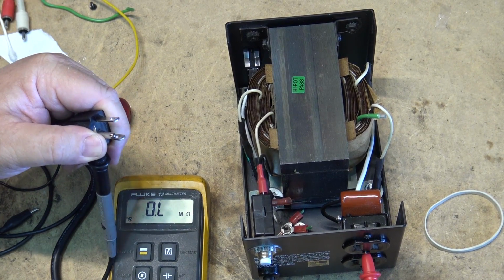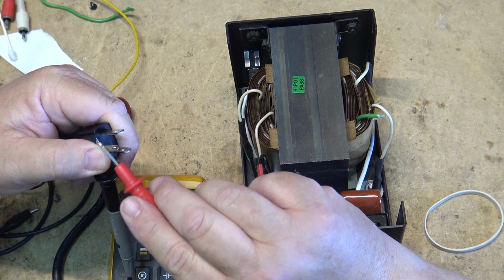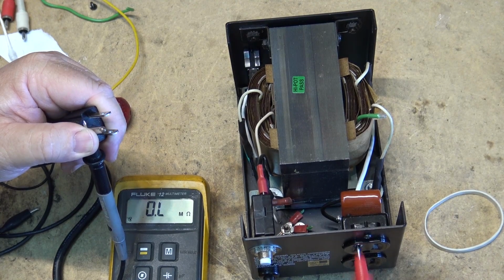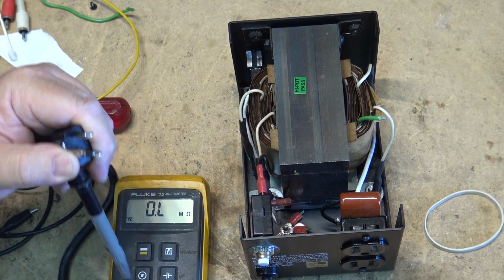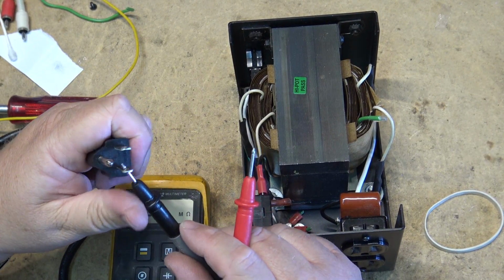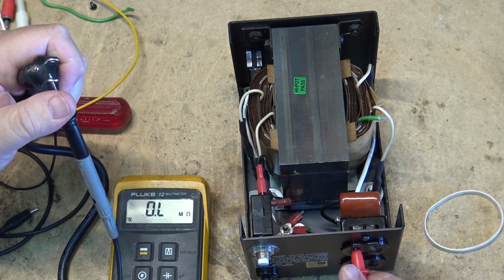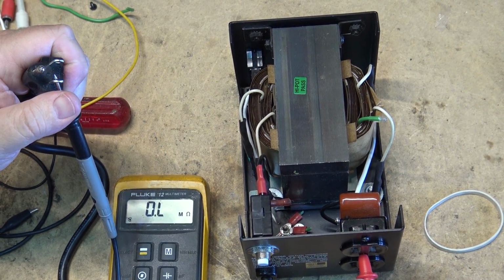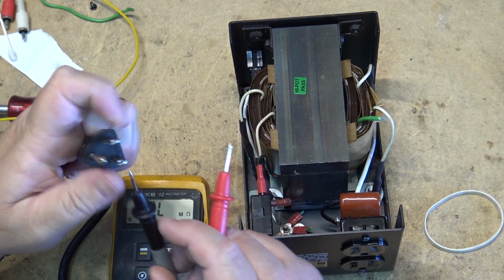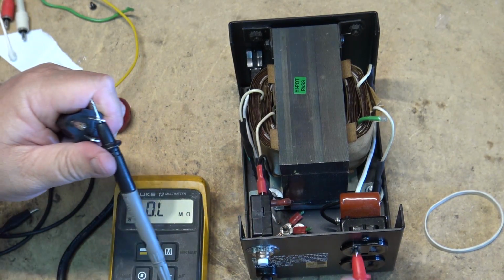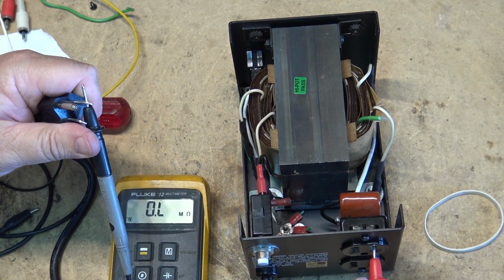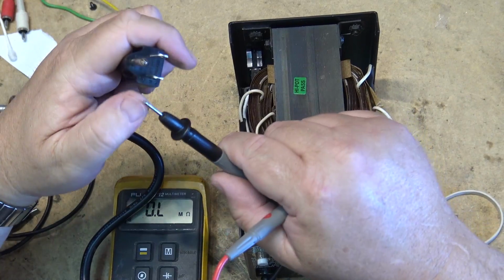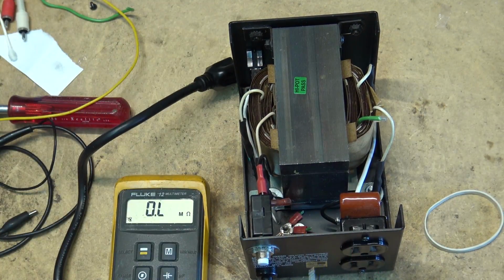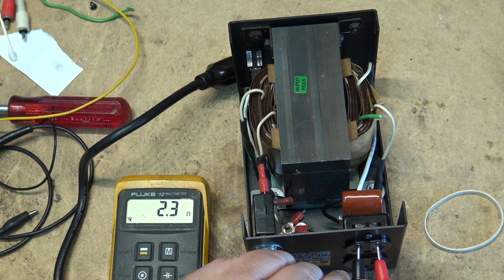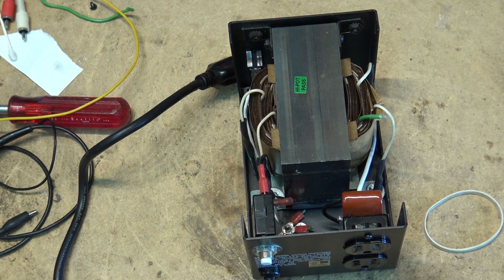If you see resistance between the ground pin and any of them, then you are not running a true isolation transformer. And the same goes for any of them - every single pin should be completely open, because there is no physical connection between any of these. The only time you should see any resistance is between the primary and across the secondary. That's the only time you'll see any type of resistance.